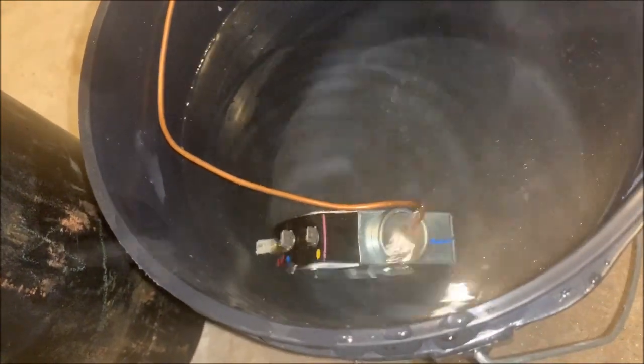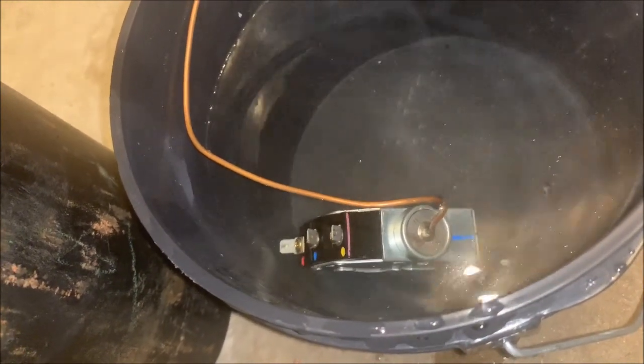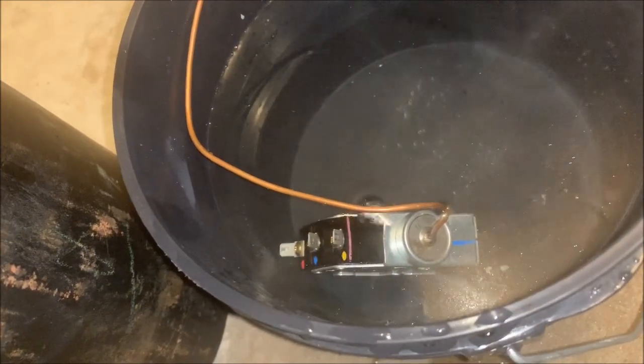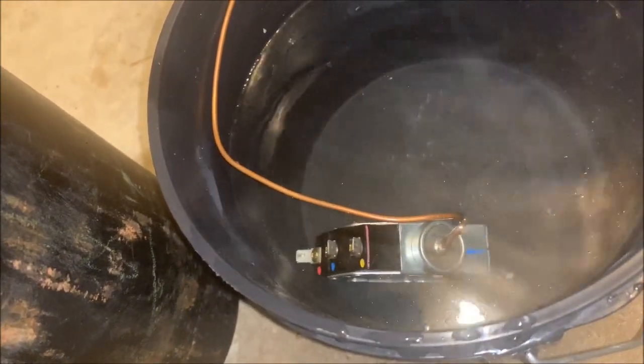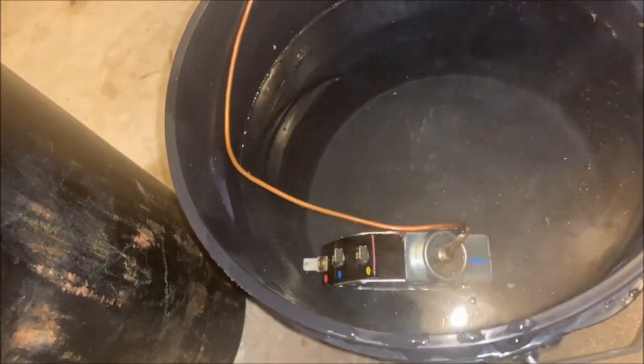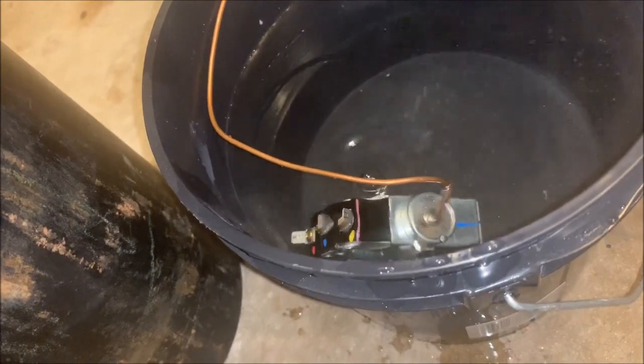So while this thing was operating, you had like 60 psi suction pressure, things started leaking, and I knew that's what it was. I went ahead and got the replacement part, put it in, and got everything going. But I thought I'd bring this thing home and verify what I thought was happening — and there you go.